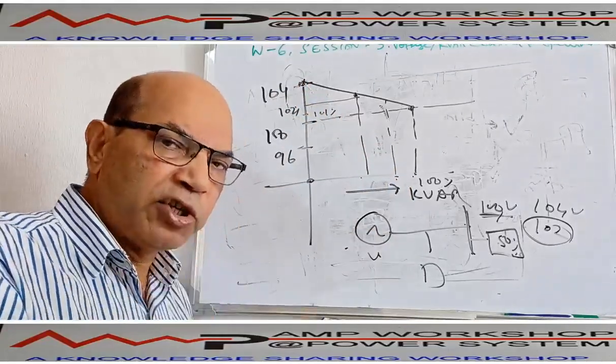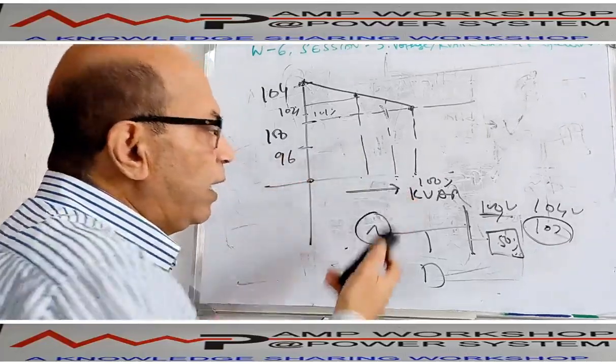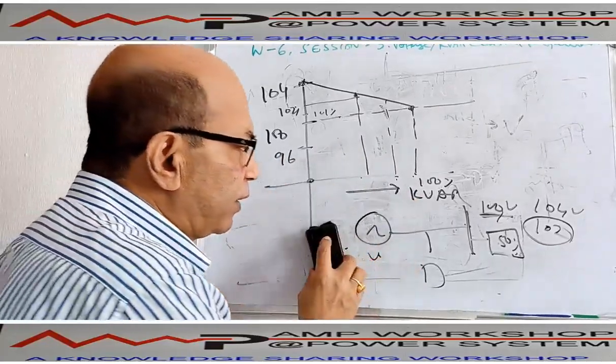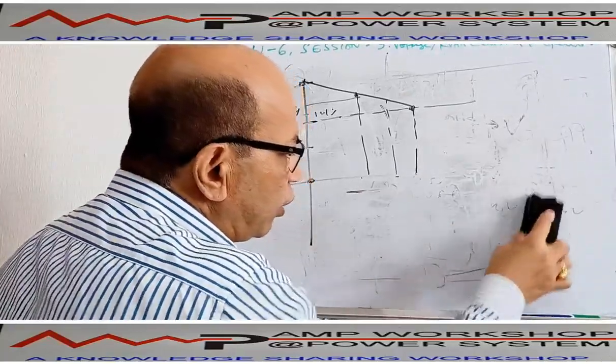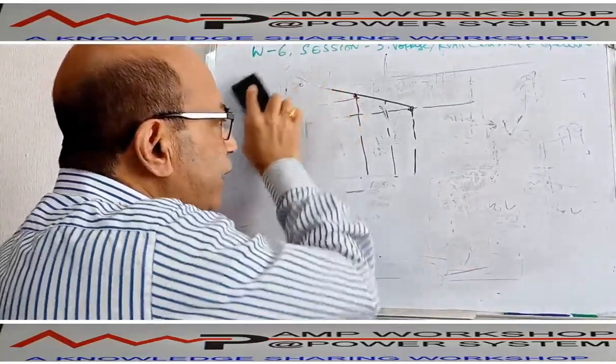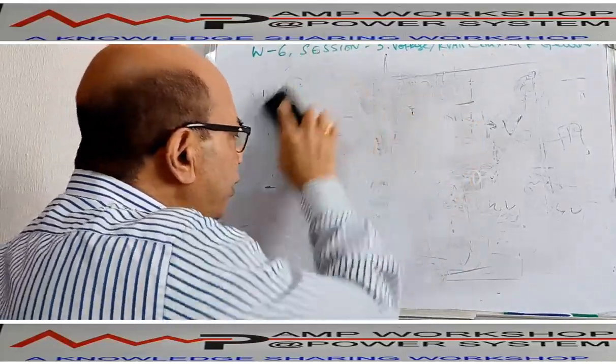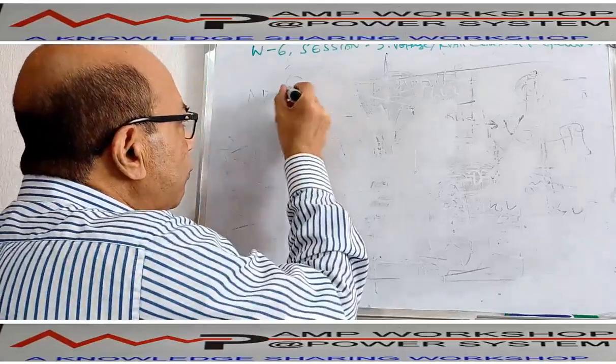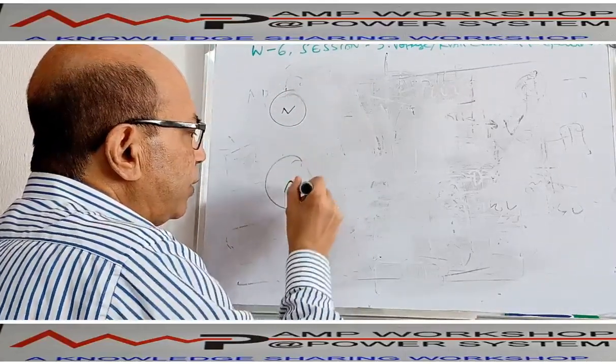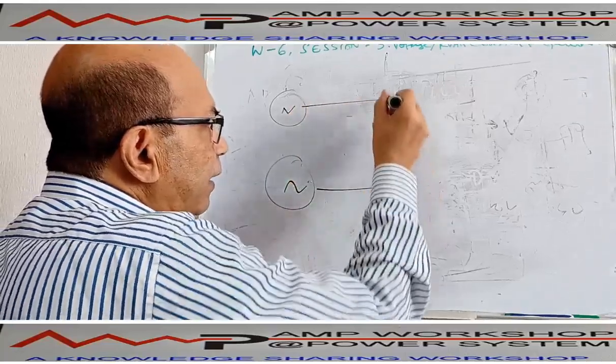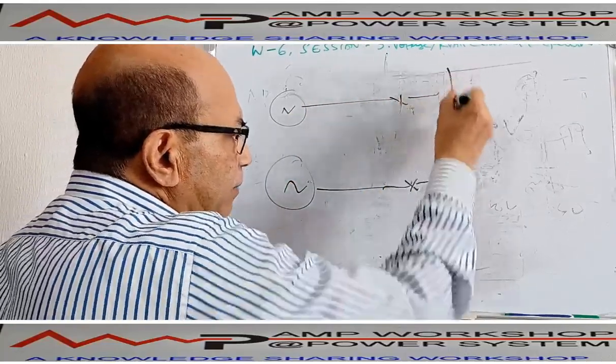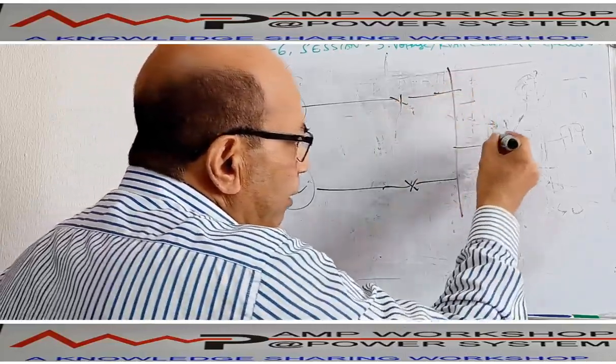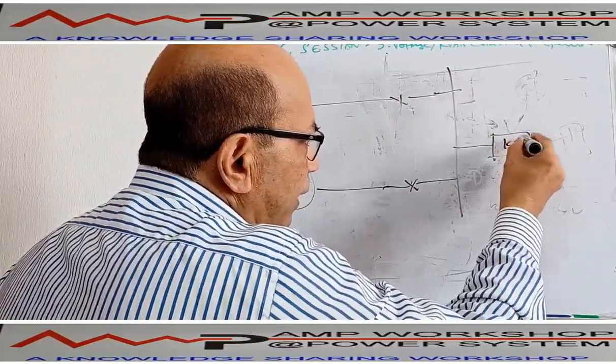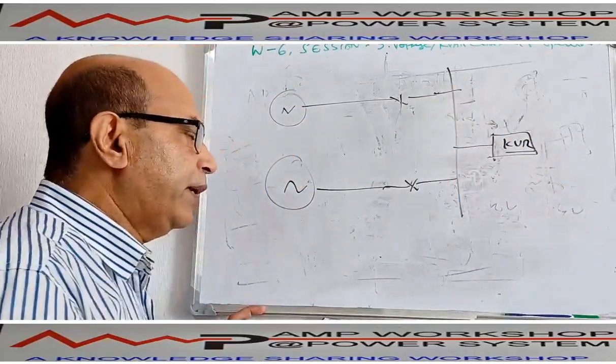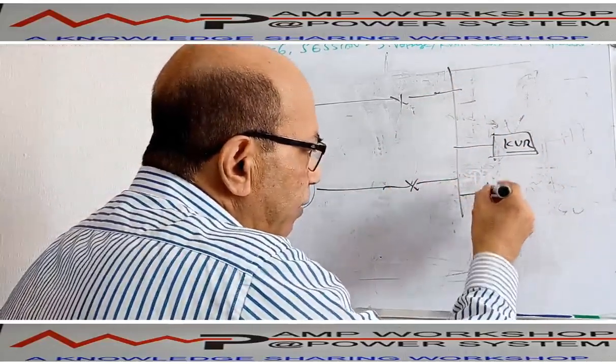Now, if there is a multi-machine system, then normally it is preferable to run the machines with the droop characteristic. Why? In that case, all the machines will take load in proportion to their droop characteristics. Suppose there are two machines running in parallel in droop mode. Suppose this is one machine and this is another machine. These machines are running in parallel with the breaker here, going to the single-line bus bar. Here you are running with a certain load. Suppose a certain KVAR is already connected, and the machine is running with that KVAR. Now some additional KVAR is given to the machine.